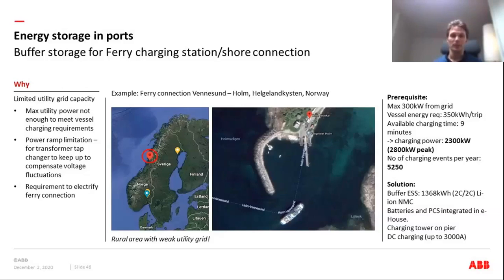So this in a way put the framework of what to achieve, and the solution we came up with there was to install a buffer battery of approximately 1.37 megawatt-hour of lithium-ion batteries. In this case, those are integrated in an e-house on shore, and the vessel is charged with DC, 1000 volt DC. This is, I would say, quite a typical solution as a buffer battery for ferry charging for electric ferries.